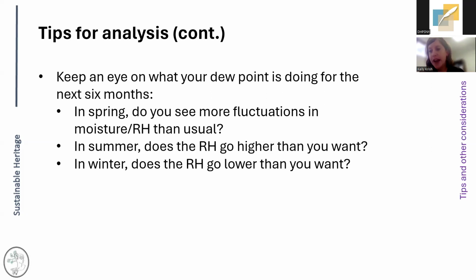Especially given the timing of this, I want to encourage you to keep an eye on what your dew point is doing for the next 6 months. Right now, this time of year, maybe into May or so, are you seeing that graph with fluctuations in your shoulder season that suggests something about the operation of the system when you're switching set points or when you have chilled water supplied? In the summer, is your RH higher than you want? Is that a result of where your ceiling is and what you're capable of doing, or is it a result of temperature choices? Work from there.